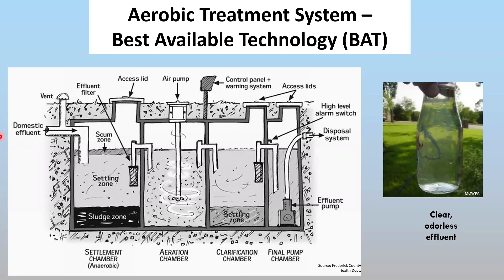Walking through this diagram, wastewater comes in from your house by gravity and goes into the first chamber — the settling chamber, much like a septic tank. Heavy solids settle down, fats and grease float, and the clarified wastewater in the middle moves into the aeration chamber. Aeration is provided by different means depending on the manufacturer — a bubbler, an agitator, etc. — supplying the oxygen needed for beneficial bacteria to break down organics and nutrients.